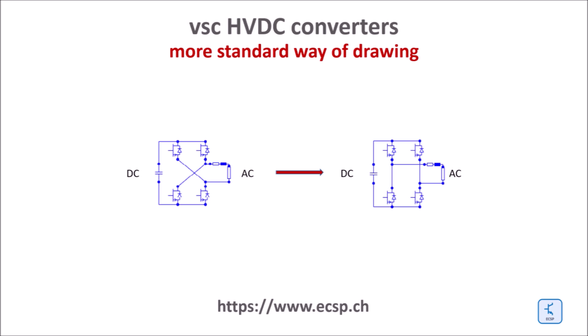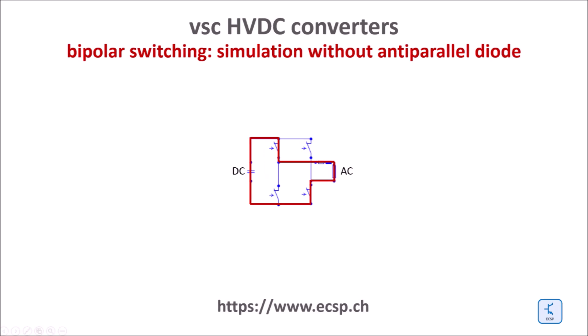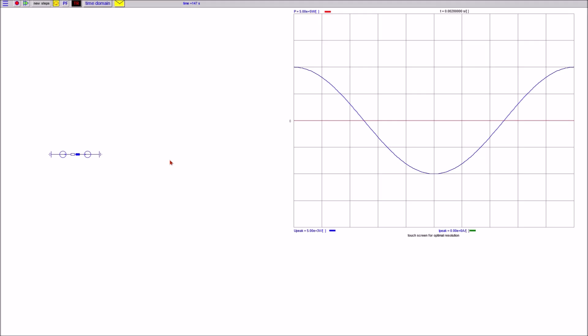From now on I will use the standard representation of converter legs. In the case of the bipolar switching arrangement, the IGBTs are switched pairwise synchronously so that the AC side output oscillates between positive and negative polarity of the DC source, as dictated by the controller output signal. If there is no time lag between the switching instances of the two legs, the anti-parallel diode can be removed without getting overvoltage.